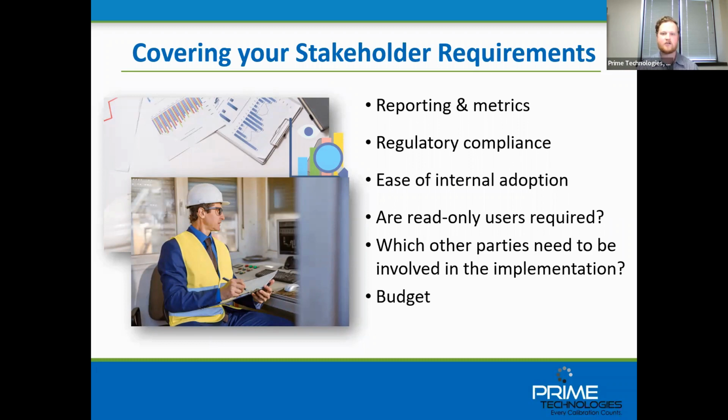So the first thing in here, reporting and metrics. It goes without saying, but not only are you going to need certificates in the reporting in the system, you're most likely going to be taking the information, your summaries of passed and failed, out-of-tolerance assets over a year, trending, specific other ISO reporting or stuff like that. You're most likely going to need that.